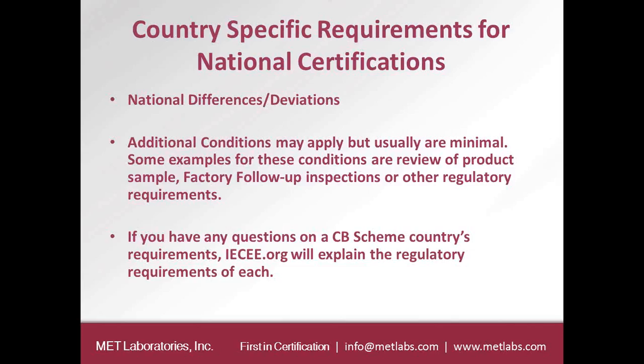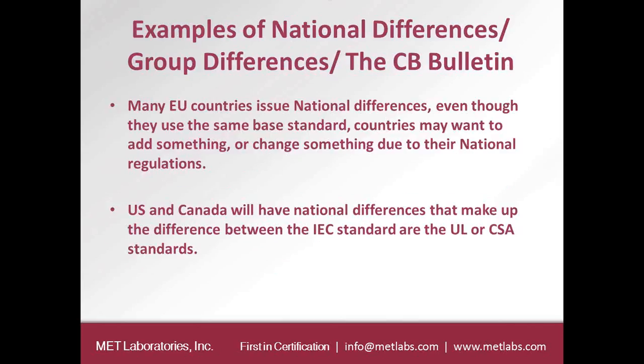Some examples of these: addressing different language concerns, cord and plug concerns, different power systems, national electrical codes, ratings and certification of subcomponents, and routine production line testing. Things like that are just a couple examples of the differences between a domestic UL CSA EN 60950 standard and the base IEC 60950 standard.